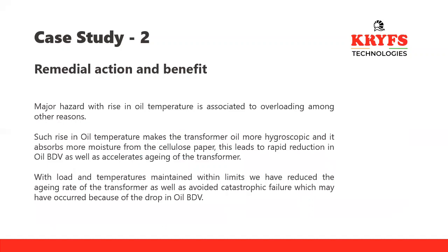We suggested some preventive actions. Not only did our device indicate the abnormalities in the transformer, but we also suggested some remedial actions to be taken. The major hazard is that the rise in oil temperature is associated with overloading of the transformer. Such a rise makes the transformer oil more hygroscopic, and it absorbs more moisture from the cellulose paper. This leads to a rapid reduction in the oil BDV value, as well as accelerated aging of the transformer. So with load and temperature maintained within limits, we reduced the aging rate of the transformer, as well as avoided catastrophic failure, which may have occurred because of the drop in the oil BDV value.